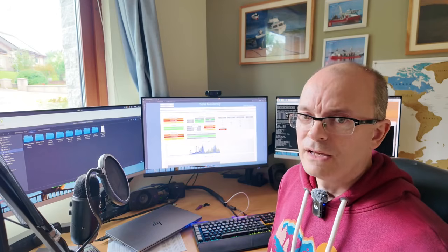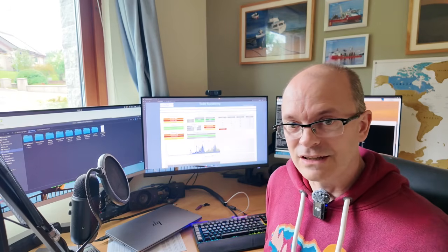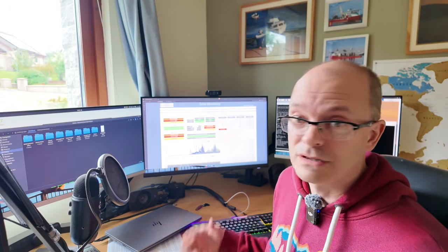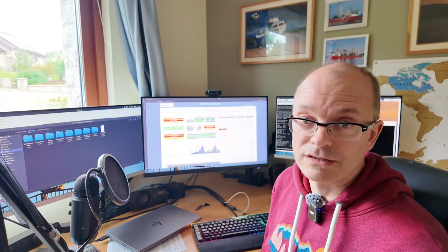switched back off. The other thing we'll do is that the SolarEdge battery is inherently AC coupling in the maximum self-consumption mode. You can't switch it on or off. If it measures an export coming from Sunsynk, it will suck that export up and charge its own battery. Something we don't want to happen.